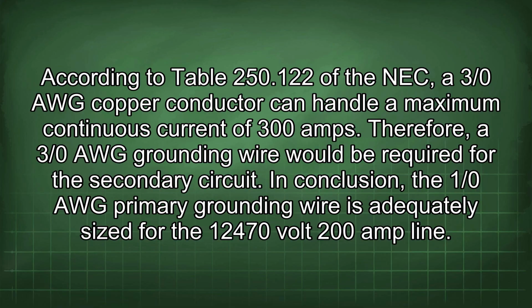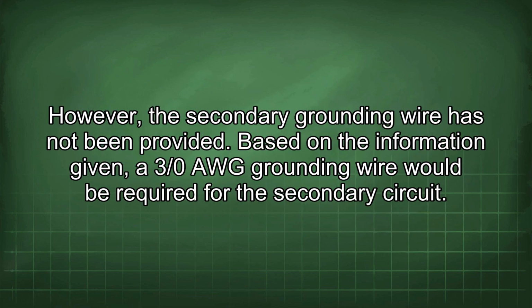In conclusion, the 1/0 AWG primary grounding wire is adequately sized for the 12,470 volt 200 amp line. However, the secondary grounding wire has not been provided. Based on the information given, a 3/0 AWG grounding wire would be required for the secondary circuit.